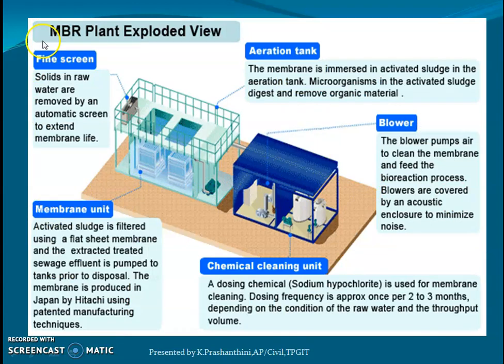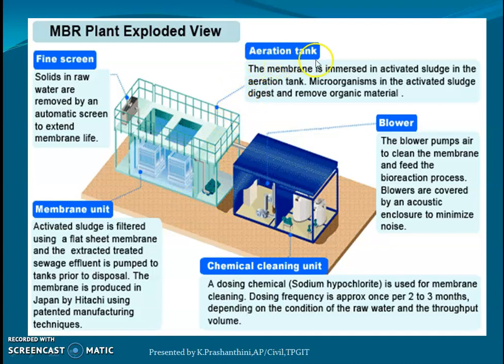The MBR plant consists of a fine screen, aeration tank, membrane unit, blower, and chemical cleaning unit. Fine screens are placed before the MBR to remove solids, thereby extending the life of the membrane. In the aeration unit, external air is introduced so that microorganisms in the activated sludge digest the complex organic matter in the wastewater and convert it into simpler organic matter.